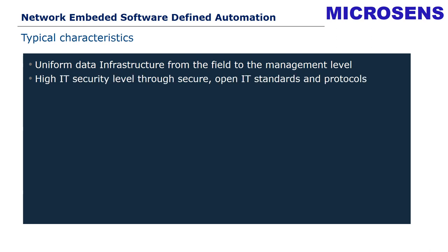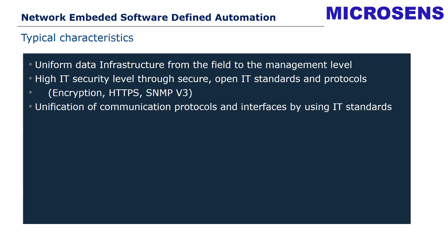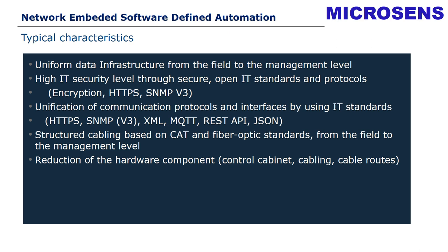Coming back to the characteristics: we have a uniform data infrastructure from the field to the management layer — this means we run only Ethernet from bottom to top. We have a high IT security level through secure, open IT standards and protocols, including encryption, HTTPS, and SNMP v3. The unification of communication protocols and interfaces using IT standards is given. We have structured cabling based on Cat and fiber optic standards from the field to the management level, and a reduction of hardware components — control cabinets, cabling, and cable trays.